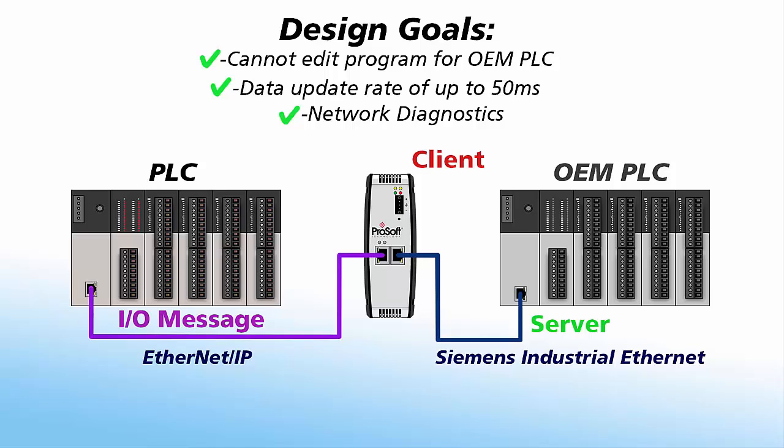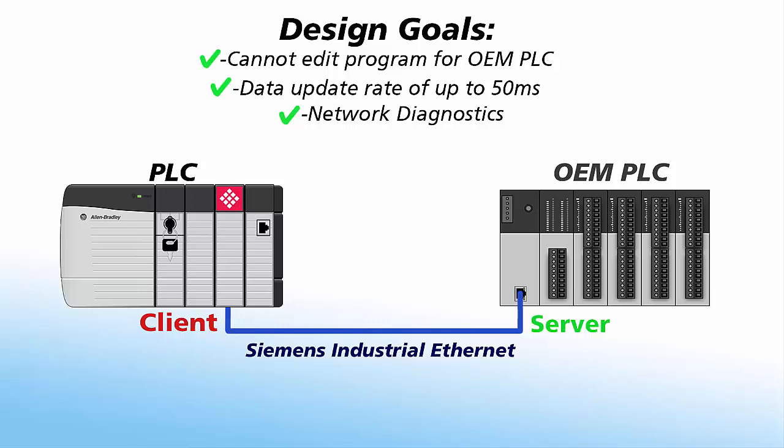The PLC will also have access to communication diagnostic tags, which allow you to use your PLC programming software to troubleshoot problems. Instead of using our gateway, our in-chassis communication module could also be used to solve this application. Our in-chassis modules use I/O messaging across the backplane to the PLC. The module's communication port would be set up as a client to talk to the OEM PLC, and this would meet all the design goals for the application and give you a more integrated solution.